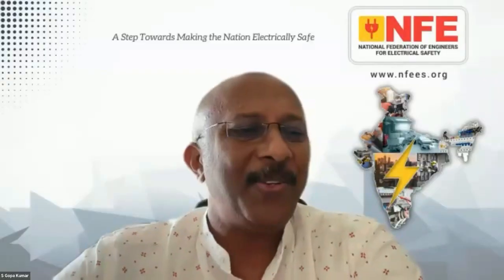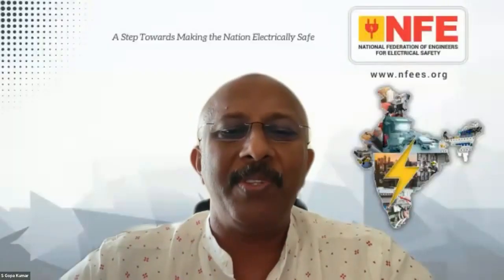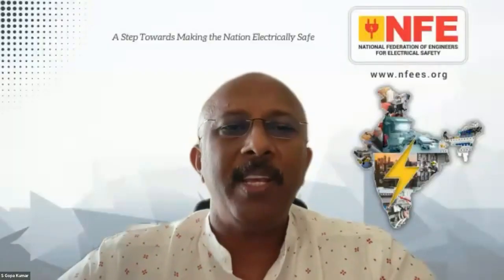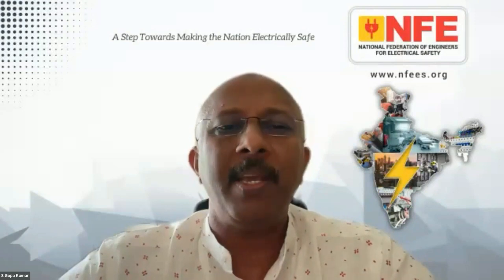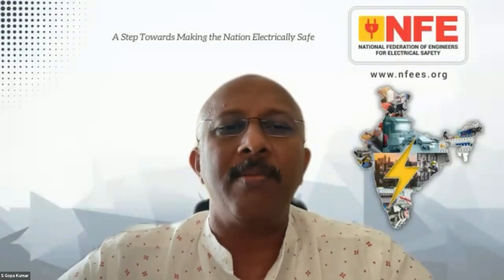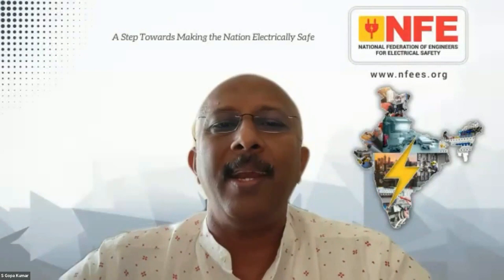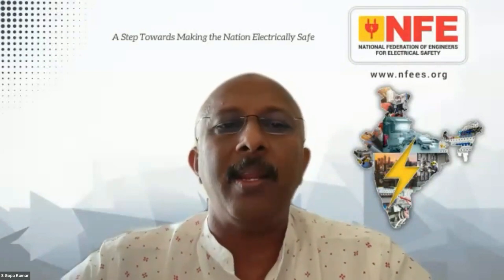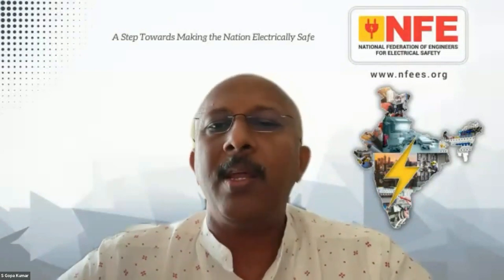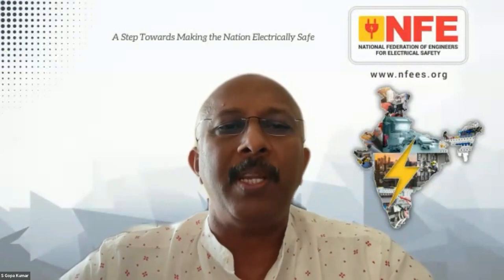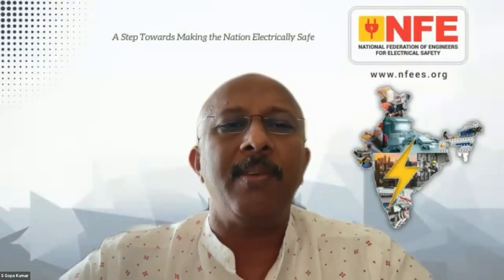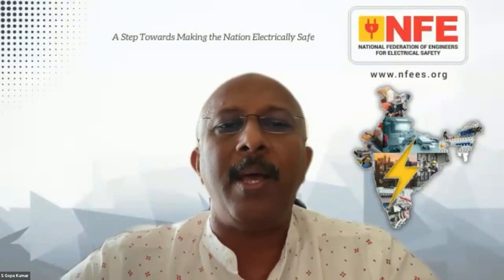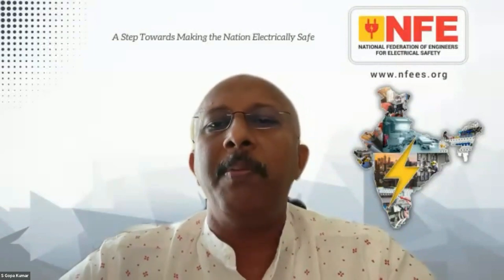But you need not per se worry much about the neutral earth potential. It is very simple to understand. For example, the voltage drop allowed in a typical installation is, let us say, 10 volt. Now you have a solidly earthed system. The neutral voltage drop may be 50% of 10 volt, let's say 5 volt. If the neutral voltage drop is more than 5 volt, the overall voltage drop at the end circuit will be higher.